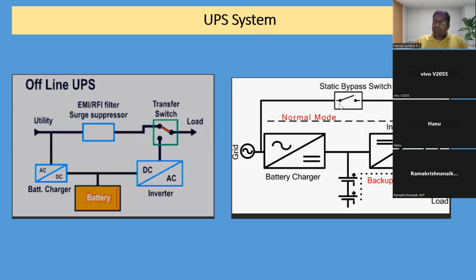Even our home inverters are nothing but offline UPS. Okay. Then come to static bypass. Static bypass is nothing but an online UPS. There is a rectifier, which is the basic concept of AC to DC conversion, because DC is required to charge the batteries, and you cannot feed DC directly. Again the inverter comes in, and DC to AC conversion happens, then it goes to the load. So you may think, why not directly give the AC, why convert AC to DC?